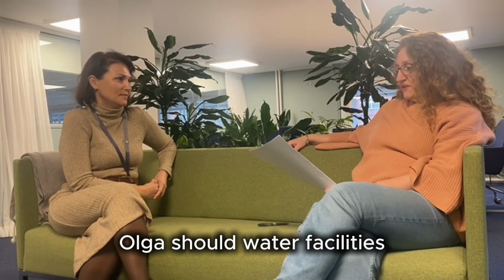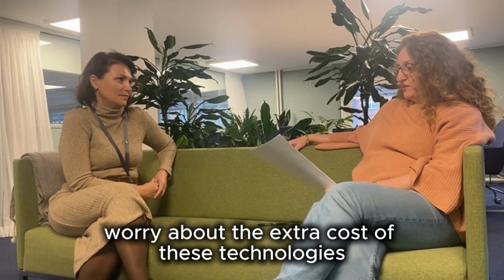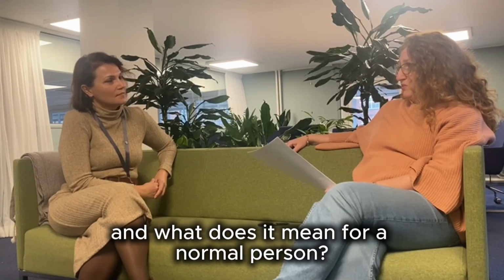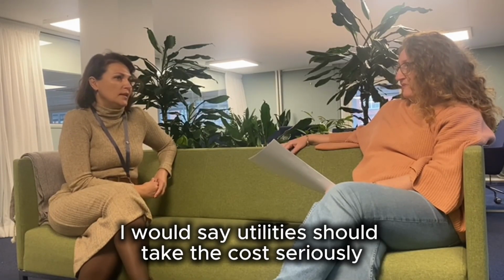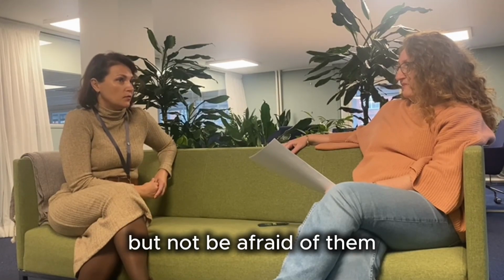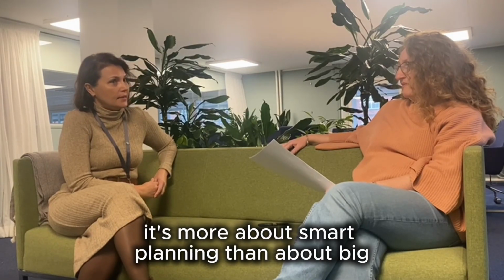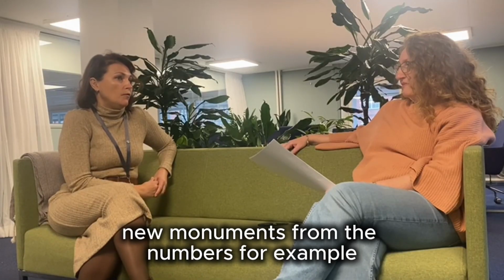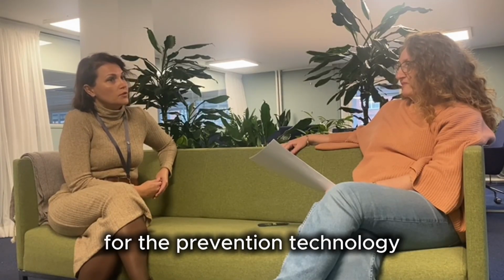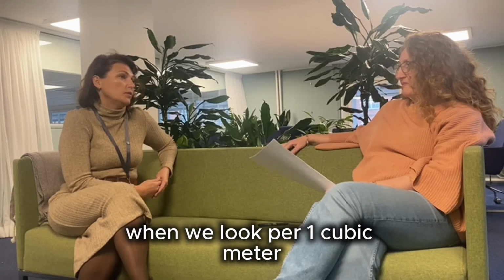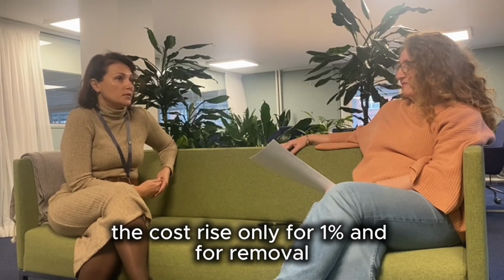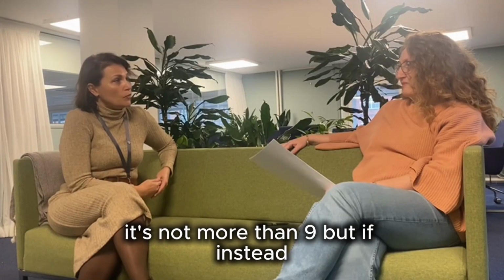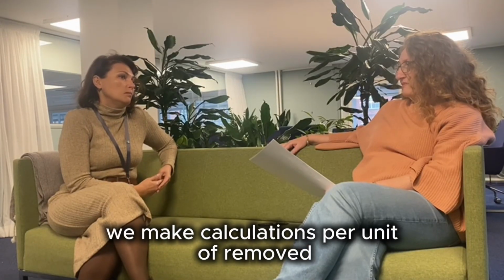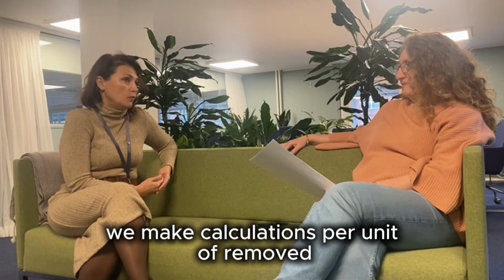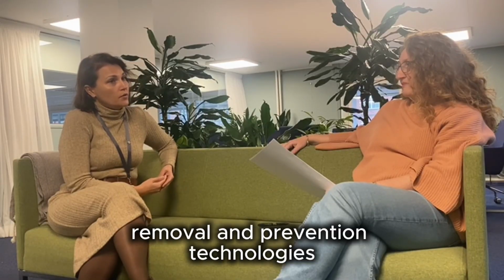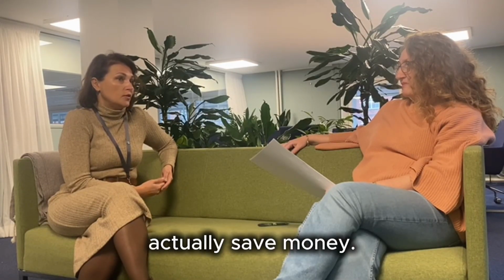Olga, should water facilities worry about the extra cost of these technologies, and what does it mean for a normal person? I would say utilities should take the cost seriously, but not be afraid of it. It's more about smart planning than about big new wonders. From the numbers, for example, for the prevention technology, when we look per 1 cubic meter, the costs rise only 1%, and for removal, it's not more than 9%. But if instead we make calculations per unit of removed THMs, then both removal and prevention technologies actually save money.